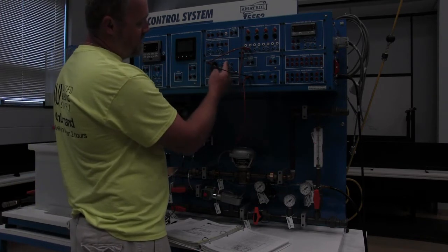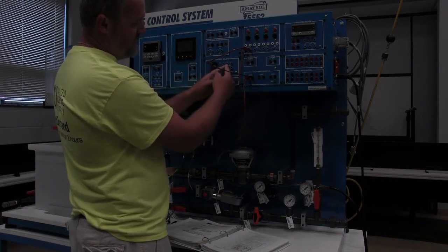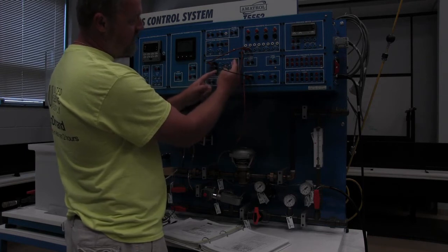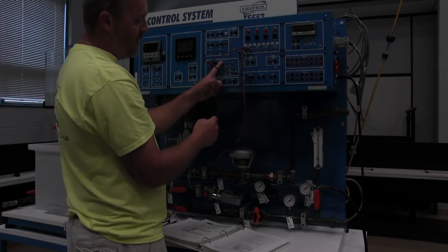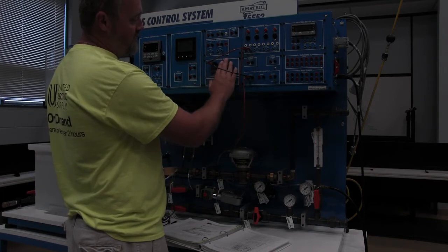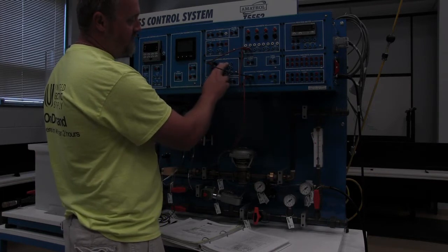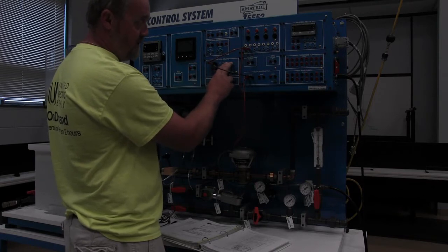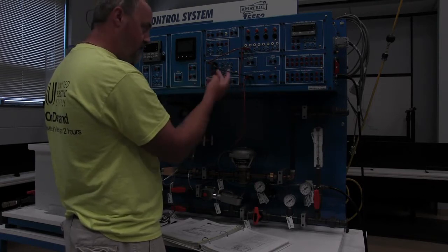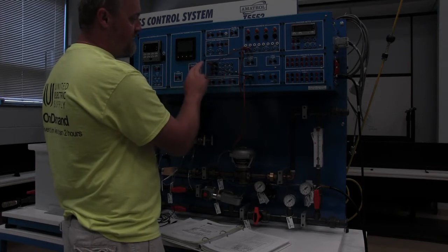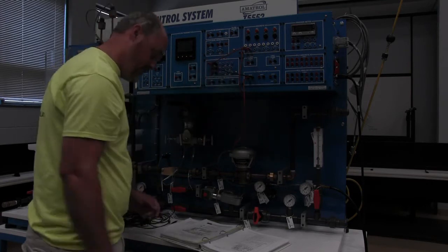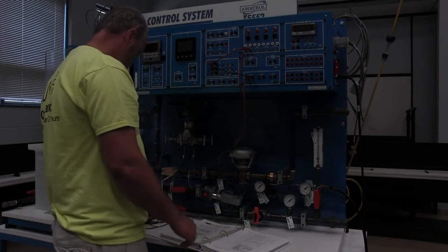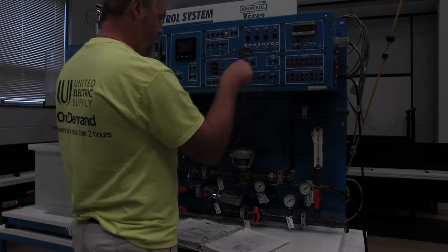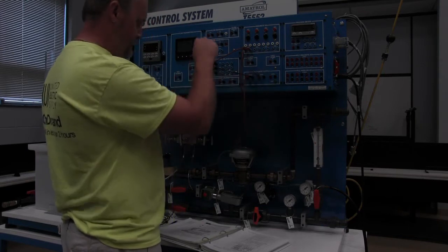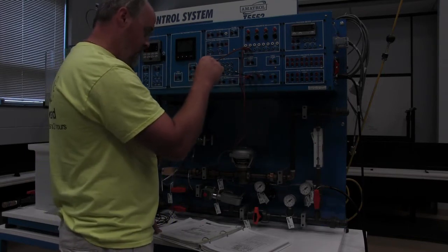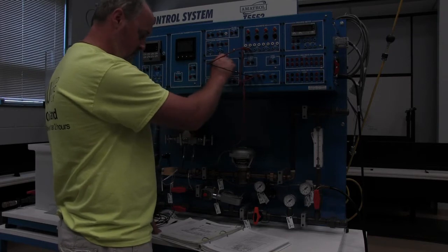Over here, the center is going to be a common, and the only reason I say that is because it's connected to each. The right is going to be a normally closed, the left is going to be a normally open. So these show in the de-energized state. In the de-energized state, from here to here is going to be open, from here to here is going to be closed. In the energized state, it's going to flip-flop those. So when this relay is energized, these will close and these will open. So now we're going to come off of 24 volt power. We can backstab or just grab another one, it doesn't really matter. We're going to go to the normally open of control relay 1.